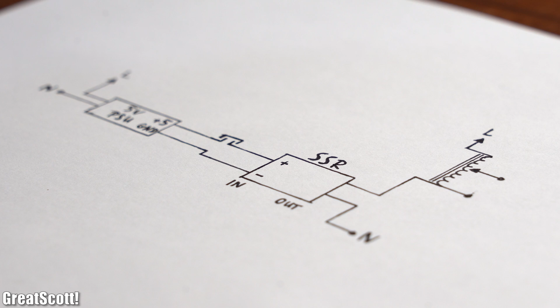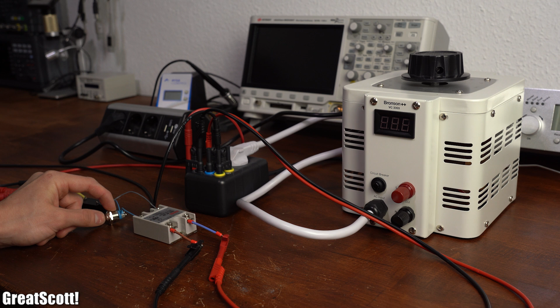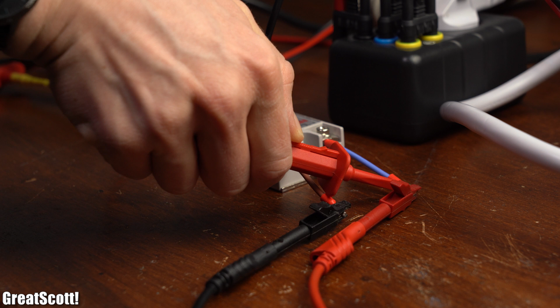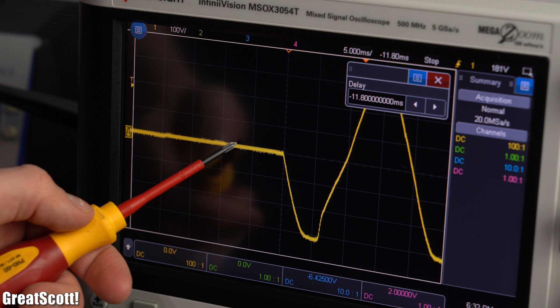After connecting it to mains voltage and the autotransformer according to this schematic, we can see that whenever I hold down the push button on the input side, the autotransformer powers up without a problem. If we observe the applied voltage waveform on the oscilloscope, we can see that the transformer only switches on near the zero point.